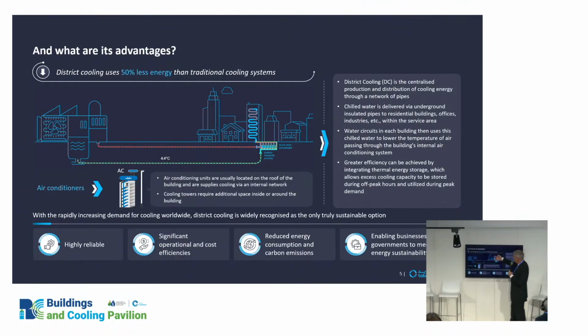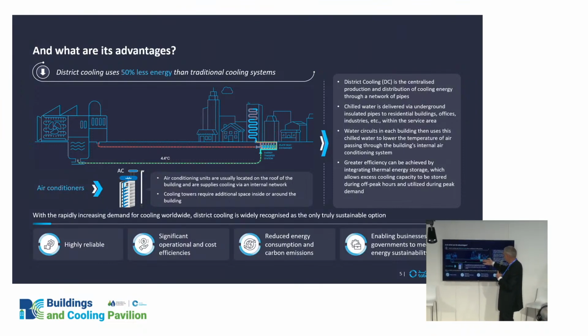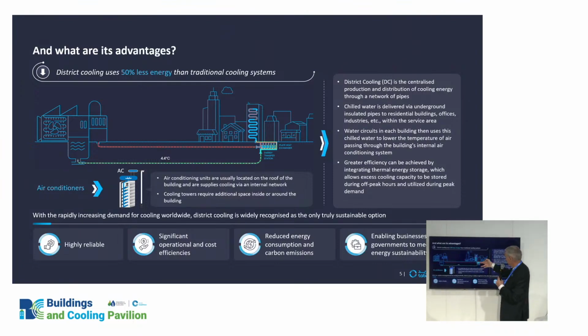The station takes the cold energy out of the water. Then there's a secondary side inside each of these different buildings that runs parallel to the chiller plates, takes the coldness out of our water, puts it into their own water inside the building, and circulates it around the building to provide cooling. That cooling, once it's cooled down all these buildings, comes back to our heat exchanger heated up. So we supply at 4.4 degrees, and it comes back to us at maybe 11, 12, 13 degrees. We take it back to the plant and begin the process all over again.